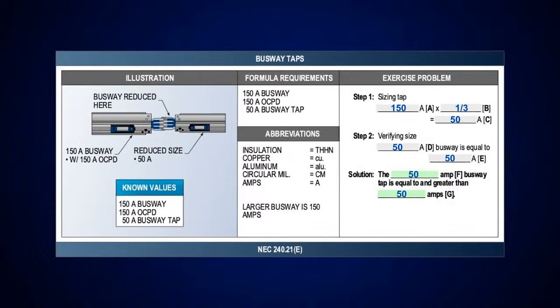All right. Well, here's a busway. I'm going to tap from a busway. How hard is this? I said everything else you take at what? A third? So here's a busway tap. I've got a 150 amp busway and I'm going to reduce it in size. What is the minimum? Well, I'm going to take it at a third. That'll give me 50 amps. So I have to have at least a 50 amp busway there per tap. I could go up to 100 amp. But once I get to 150, guess what? It's no longer a tap at that point. Okay?